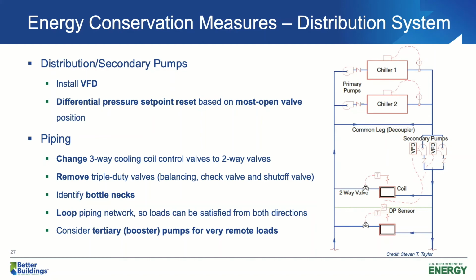Distribution system. Install VFDs on your secondary pumps and reset your DP set point based on the most open valve position. This way we can provide just the right amount of pressure to the system so that all cooling coils will have enough chilled water flow. Change all three-way control valves to two-way control valves. This way we will convert the system from a constant flow system to a variable flow system and save a lot of pump energy. Remove all triple duty valves.